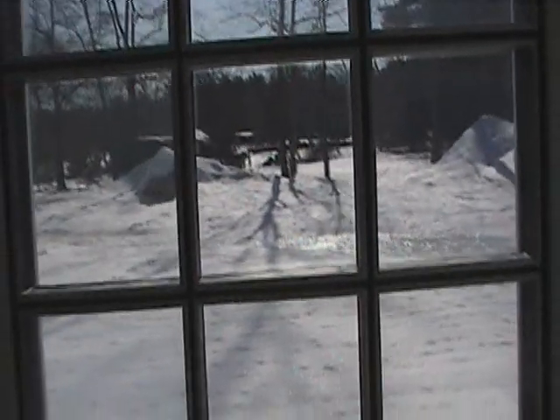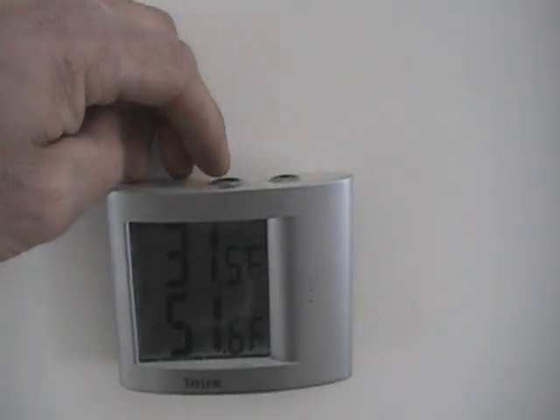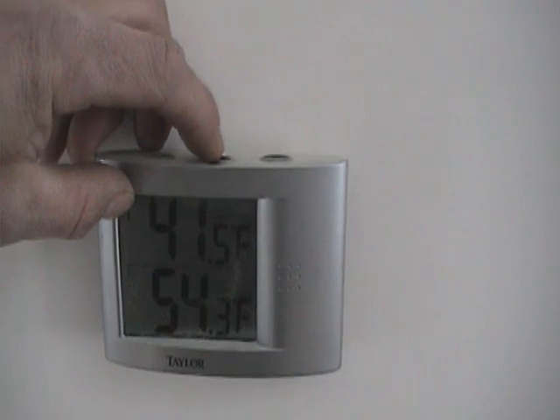Here are just a few hours in. So they'll continue to warm up over the course of the day. The house has warmed up itself — I'll show you the thermometer, it's right over here. You can see we're starting to install the kitchen cabinets. So the indoor temperature right now is 51.6 degrees, outside is 31.5. I reset the minimum temperature yesterday. We had a maximum temperature yesterday — went up to 41.5, the house came up to 54.3. And then our low time temperature: last night went down to 21.6, and the house went down to 49.6. So from 49.6 to 51.6 today, the house itself has warmed up two degrees, even though the temperature hasn't come up above freezing yet today.